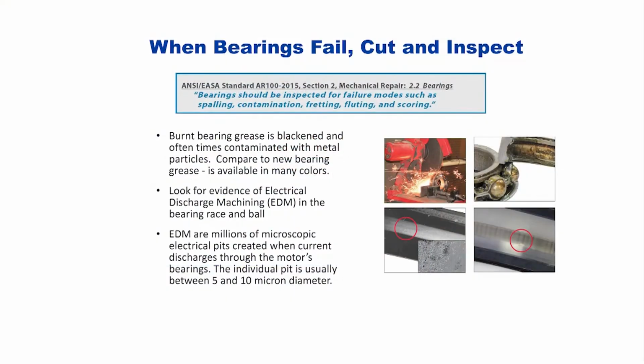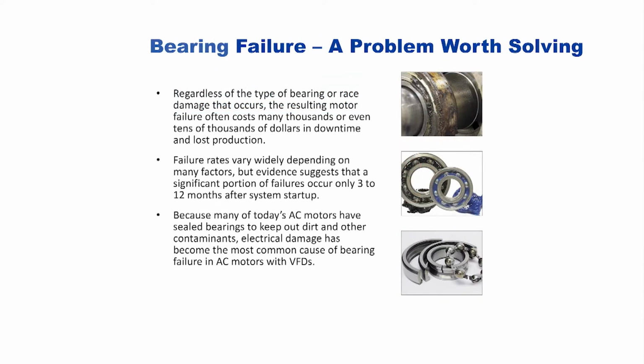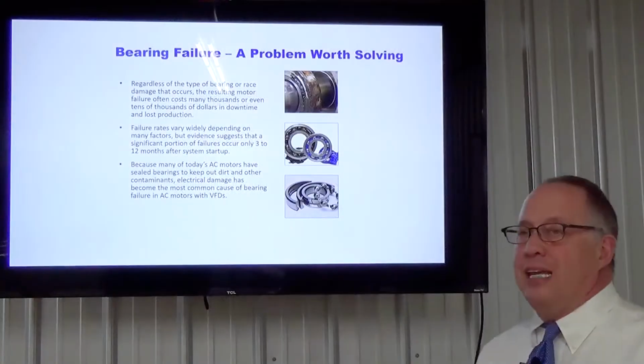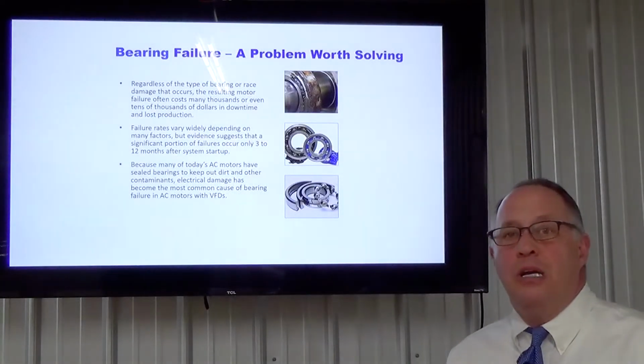EDM produces millions of microscopic electrical pits created when the current discharges. The individual pit is usually between 5 and 10 microns, small, but over time enough to cause you damage and freeze up. Bearing failure, a problem worth solving? Regardless of the type of bearing or race damage that occurs, the resulting motor failure can cost thousands, even tens of thousands of dollars if it's in production.